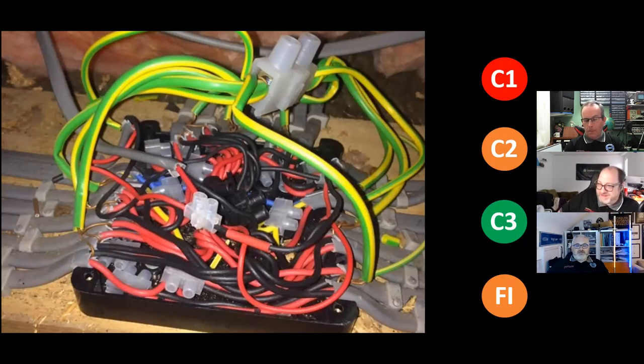I believe it's some sort of central heating cluster mess. I've done a house where we had three boilers, 7 cylinder stats, 8 thermostats, a number of valves. It was a listed building. All the central heating wiring had to go in the loft. You ended up with a big piece of plywood on the wall. You get all your cables up, then you've got to figure out how it all works, and if you've got a priority and changeover switch for the boilers, pump overruns. So this is the sort of mess you can get with the old wiring schemes. And somebody's obviously got to the point where they've done the follow the live game using connector blocks, and then said, sod the CPCs, I'll connect them later.